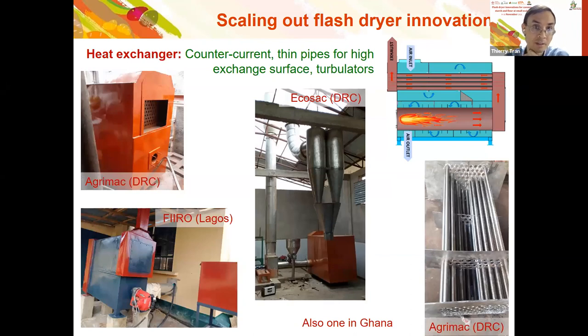Another key finding for improving flash dryers is the heating system and the heat exchanger. Several current heat exchangers have a low exchange capacity and cannot transfer all the heat generated by the burner to the air for drying. So we also developed a new design of heat exchanger with a counter current flow. The principle is to have the fumes from the burner circulating in one direction and the fresh air going to the dryer in the opposite direction.